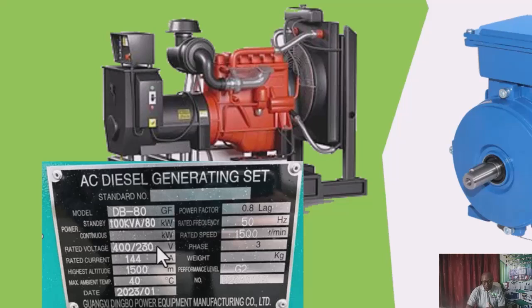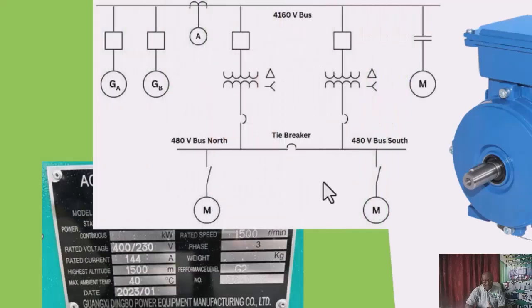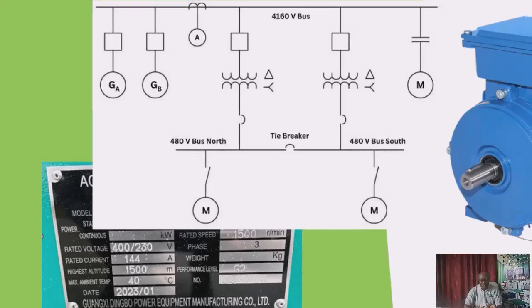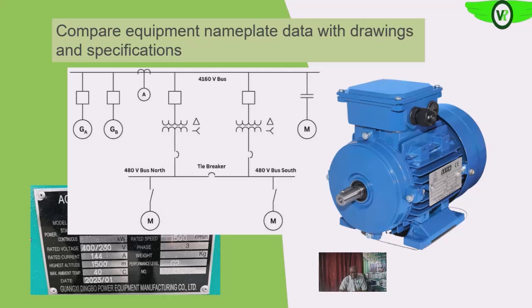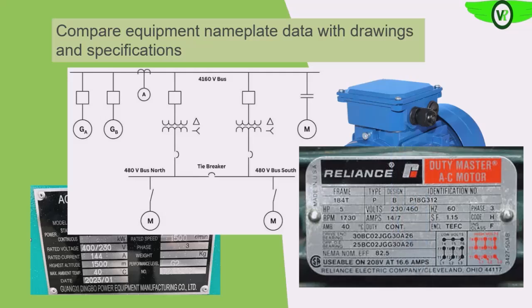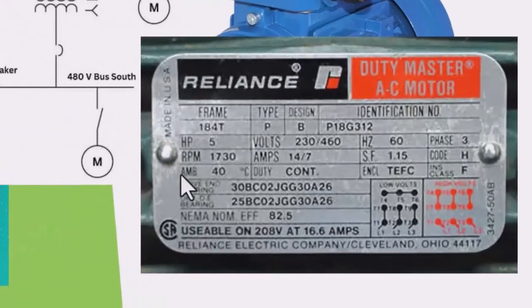So if you have this kind of information, it means that the output voltage here should be 4,160 volts. Again, you also look at the load that the generator will be feeding, which will be clear on the single line diagram too. Okay, so the load on it will determine the current that will be flowing back to the source, that is the generator. So that will also determine the amperage of your generator. So these are the little features that you look at, okay, to determine that the generator actually meets the specification that you actually want. So on the electric motor, you also look at the nameplate.